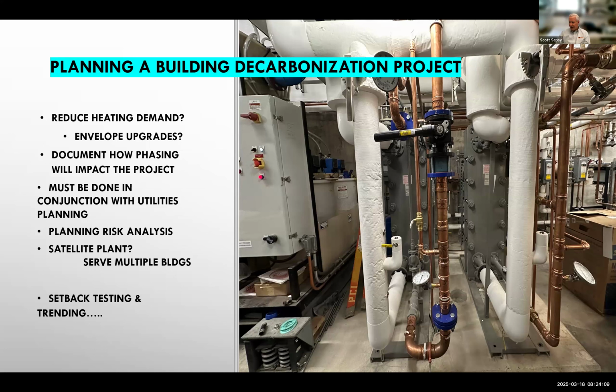Add valves that can phase and sectionalize your hot water network. Perhaps the perimeter system is the first to run on low temperature hot water and the reheats may be flipped later. You may need temporary systems as part of a phasing to keep your equipment in operation. The contractors and the construction managers should know as much about phasing as possible to accurately plan and price their work. Reusing steam piping for hot water, either supply or return, might help with phasing and save money. Condensate lines will be likely too small to reuse, but the steam piping could be reused.